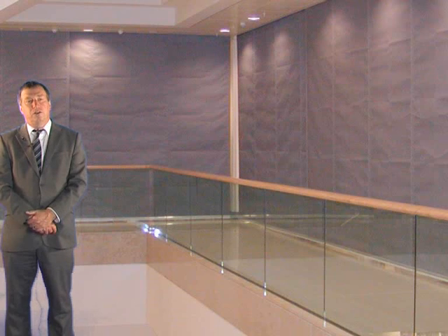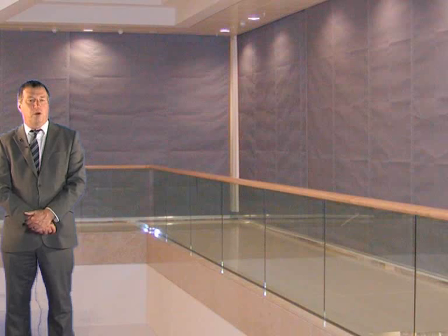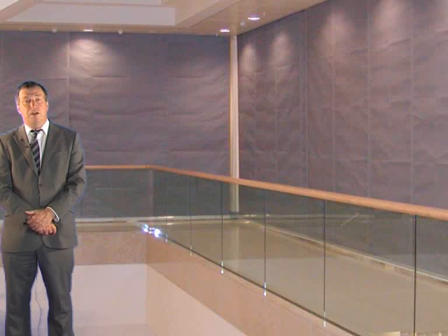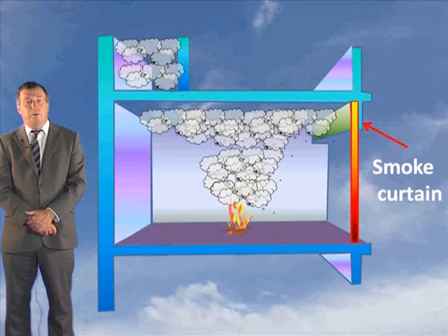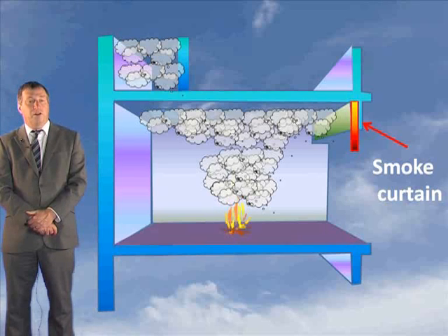The next area we're going to talk about is smoke curtains. Now, it's common to use smoke curtains to form the reservoir in which the smoke will be collected. They can also be used to separate the main smoke reservoir and adjacent spaces which may be higher than the design smoke layer base. In these cases, the curtains will be deployed from the ceiling either to the floor or more likely to some appropriate and calculated depth below which it has been demonstrated that smoke will not descend.